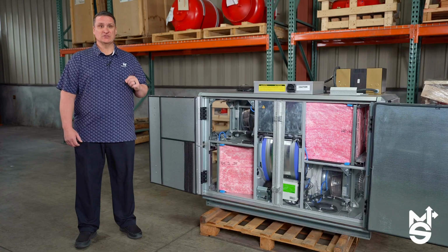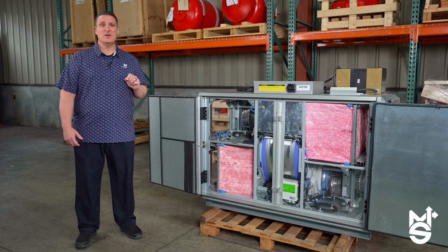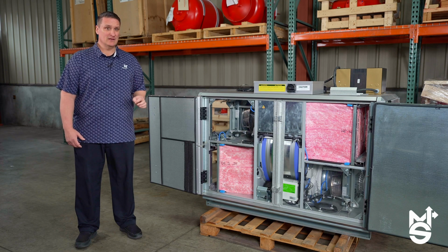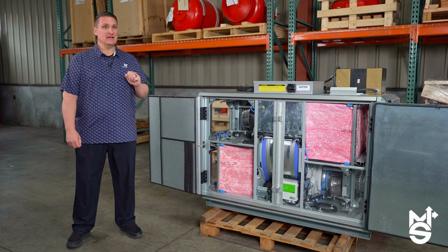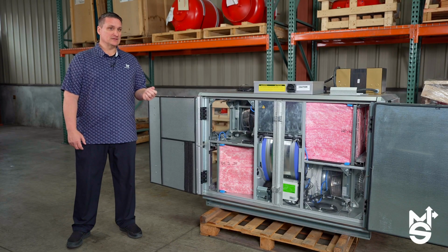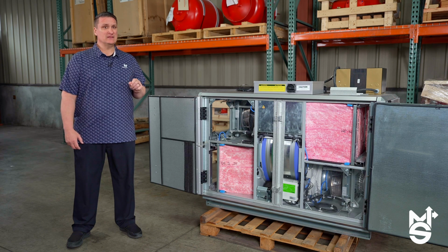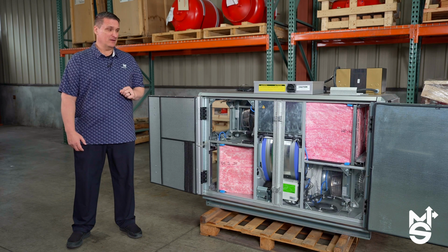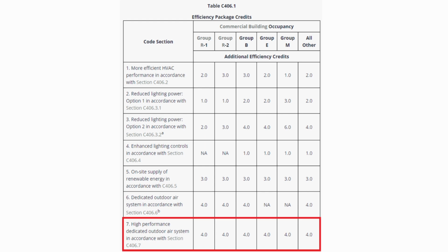All fans include integrated, accurate airflow measurement sensors to allow for direct control of airflow in the system. The airflow is adjusted in real time as an example for air density correction, filter loading, and system pressure changes to ensure ventilation comfort is always met. The fans are engineered for strict acoustical performance by attenuating sound and vibration internally. No external isolation is required. All Swegon fans are designed to be serviced quickly by trained staff. Swegon fans are mechanically and electrically connected with quick release harnesses. This is designed to replace a fan with minimal tools in a matter of minutes. With our efficient Swegon fans, we designed to meet stringent energy codes such as the City of Seattle of 0.5 watts per CFM or the Washington State Energy Code of 0.769 watts per CFM.